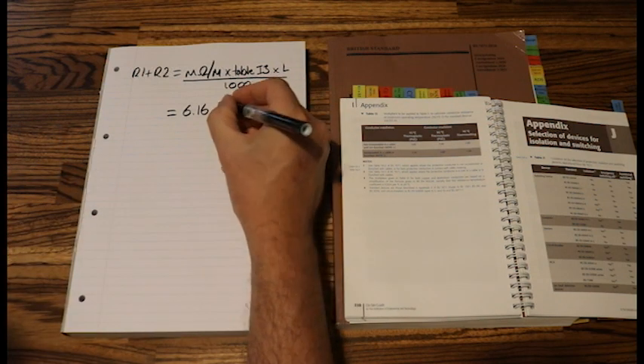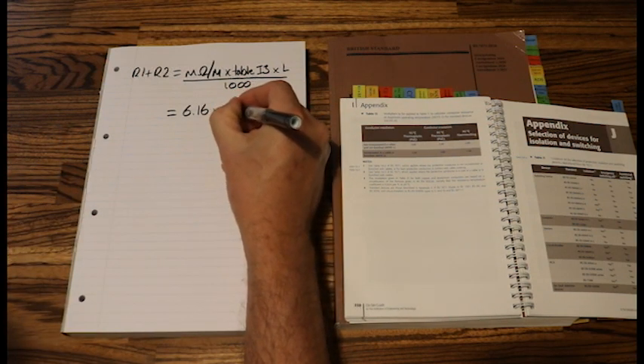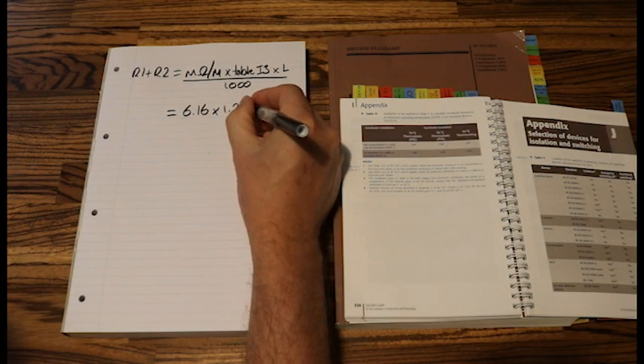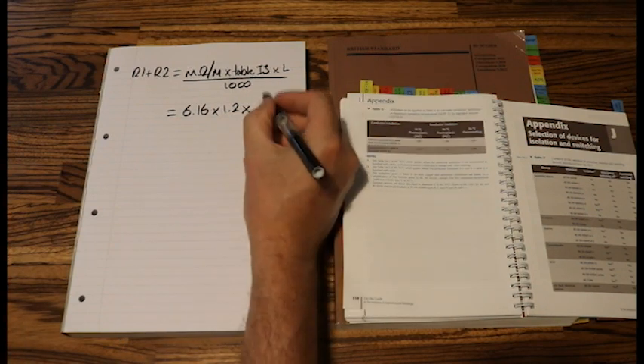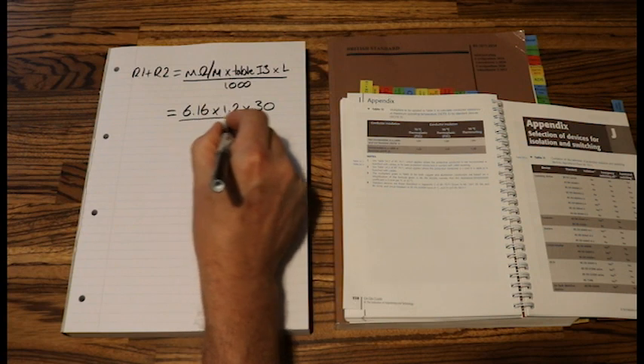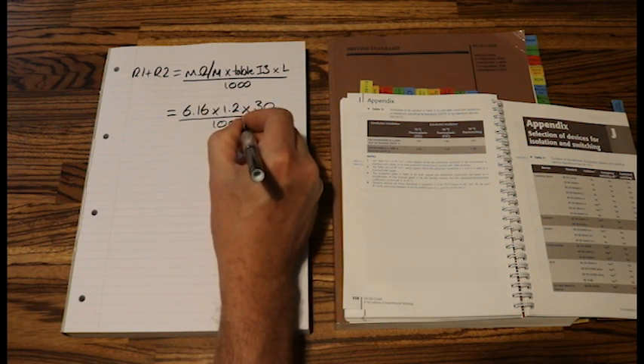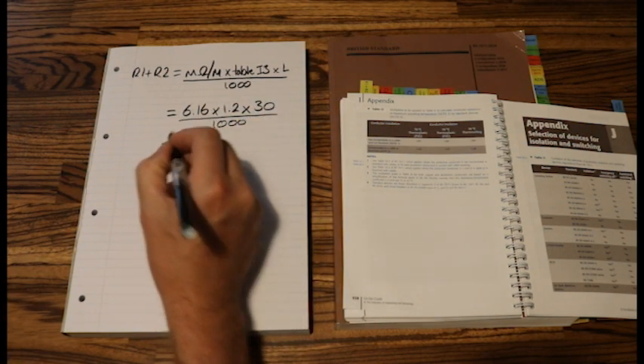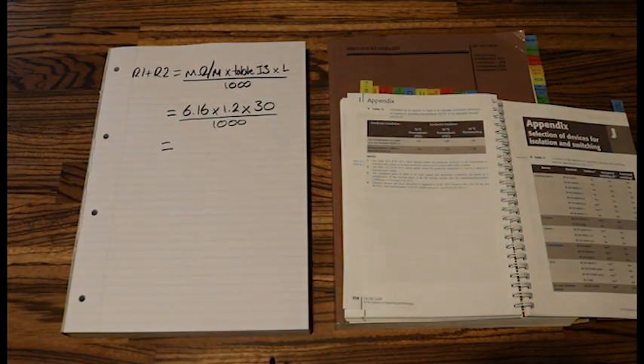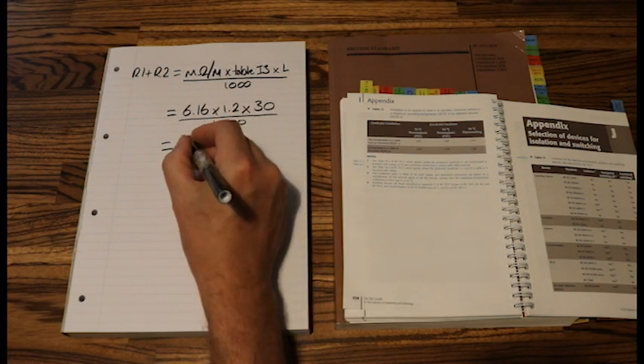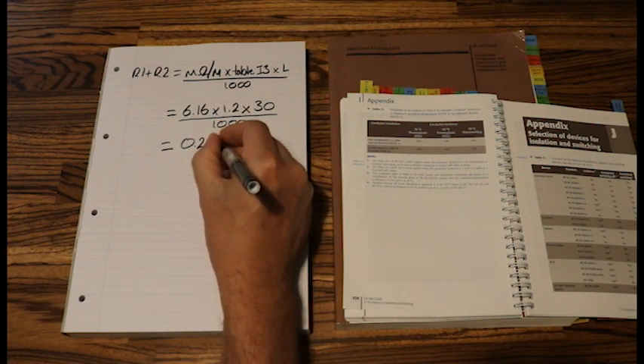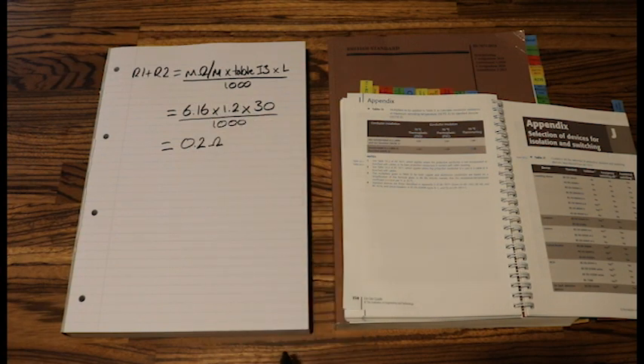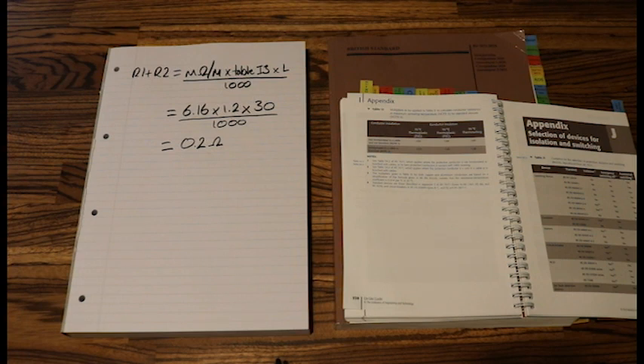So we'll put that times 1.2. And L is the length. For this question the length was 30 meters. And then over 1,000. So if you punch those values or those numbers into our calculator, we will get 0.2 ohms. And that is how you work out your R1 plus R2 for that type of question.